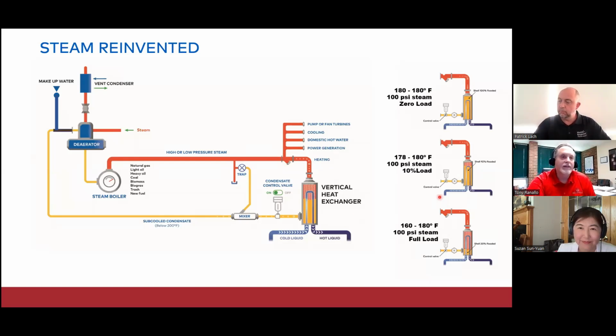Over here on the right is a little illustration of just three different loads. At the top, we've got our zero load, which means that we don't need any heat in our water system over here, and we've got a fully flooded heat exchanger. As we get a call for heat, and we need more heating out on the hydronic end of things, we will start to unflood the heat exchanger by opening our condensate control valve. This allows us to expose part of the heat exchanger.